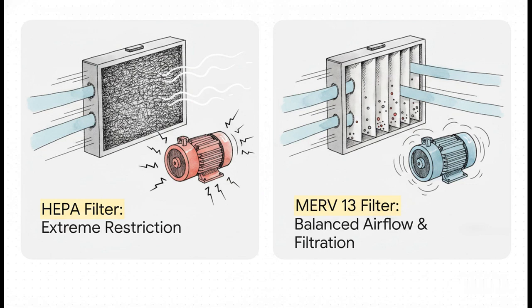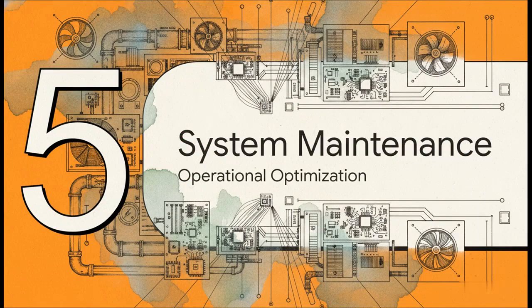On the flip side, MERV 13 filters are highly efficient. They capture those ultrafine 0.3 to 1 micron particles like wildfire smoke and viral aerosols, but they maintain sufficient HVAC airflow. Because of this, MERV 13 is actually the superior professional choice for whole-room, rapid-volume air cleaning through central systems. You maximize your total CADR without destroying your mechanical infrastructure. Module 5, System Maintenance and Operational Optimization.